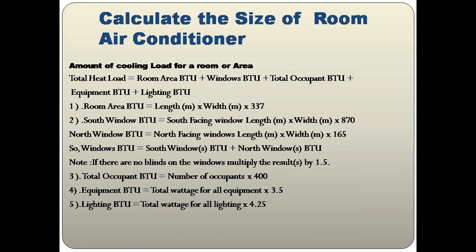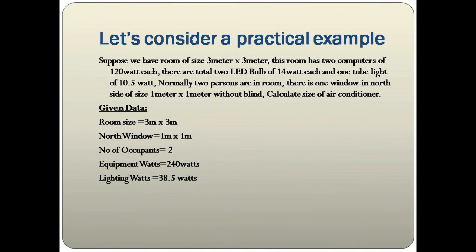For Lighting BTU: calculate the total wattage of all lighting and multiply by 4.25. Now let's consider a practical example. Suppose we have a room of 3 m × 3 m with two computers of 120 watts each, two LED bulbs of 14 watts each, one tube light of 10.5 watts, and normally two persons in the room.